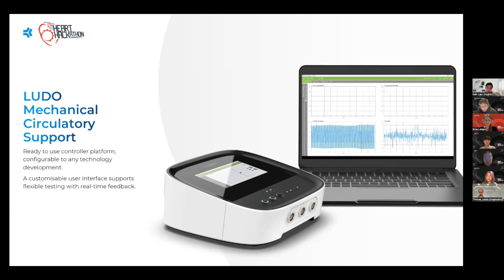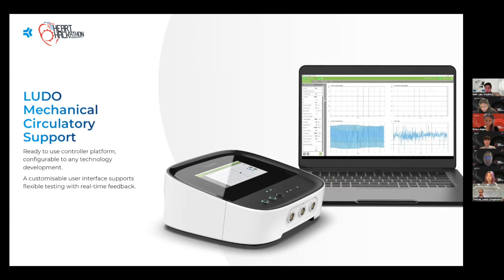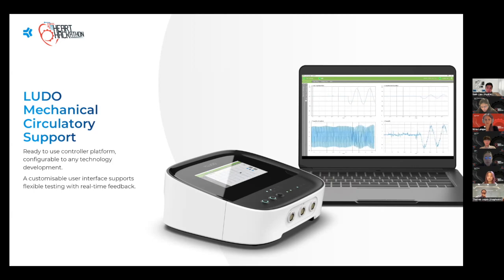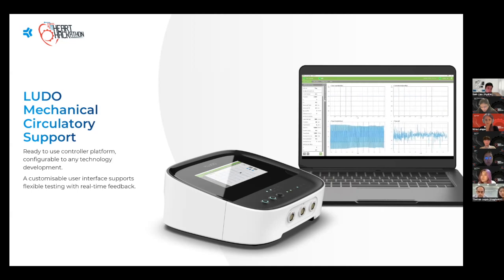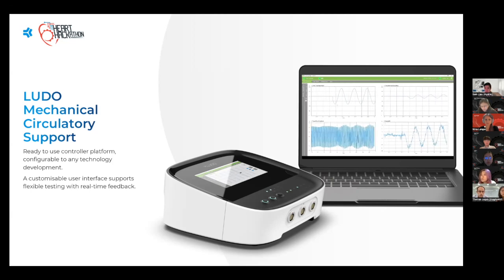It is also unlikely that any off-the-shelf product will meet all the requirements for a particular device, hence the need for customization. Since Hydrix has developed the Ludo platform from fundamentals, we have full visibility of all aspects of the controller, including both hardware and software, which can be tailored to each unique pump design. For example, Ludo can easily integrate both physiological and motor control algorithms, but they are structured in such a way that they are independent of each other, meaning that any changes in the physiological control do not affect the motor control and vice versa.